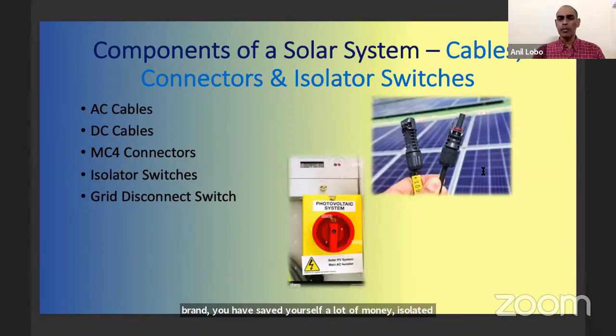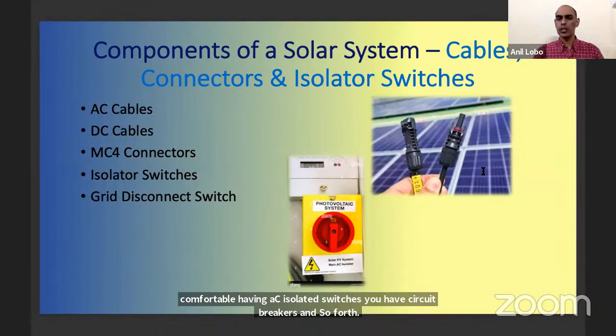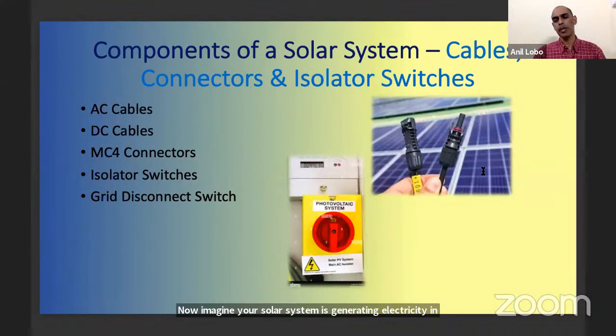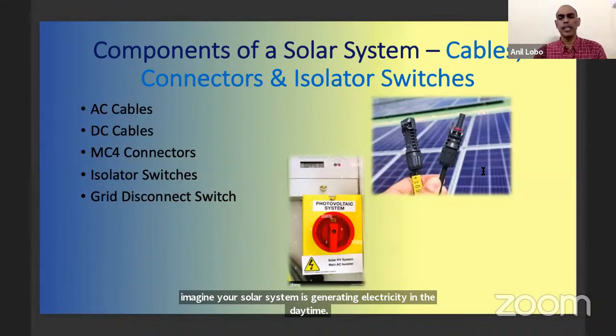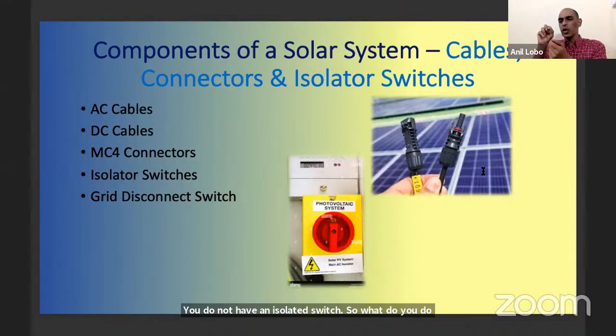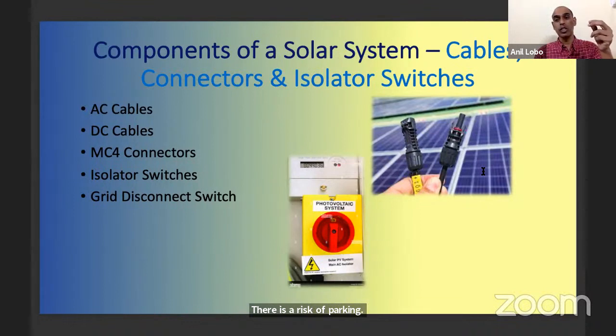Isolator switches are very important. People are very comfortable having AC isolator switches, circuit breakers and so forth, but it's very important to have a DC isolator switch too. Why is that important? Imagine your solar system is generating electricity in the daytime and you want to do some service or maintenance, but you don't have an isolator switch. So what do you do? You take your screwdriver, loosen the cable, and try to pull it out as quick as possible. There is a risk of arcing, and if the voltage is high, say 400 volts DC, there's a risk you'll damage your inverter, or even burn yourself, or cut off your hands.